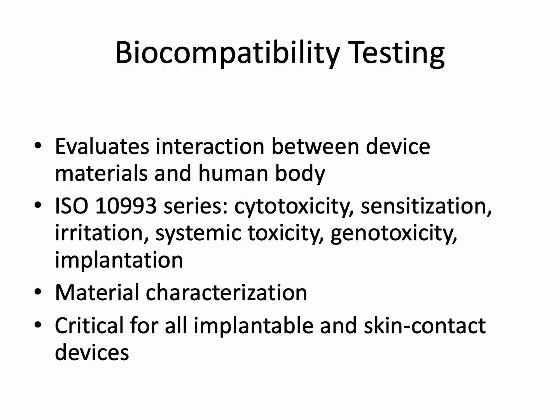Biocompatibility testing assesses how device materials interact with the human body. ISO 10993 provides a structured framework covering cytotoxicity, sensitization, irritation, systemic toxicity, genotoxicity, and implantation studies.